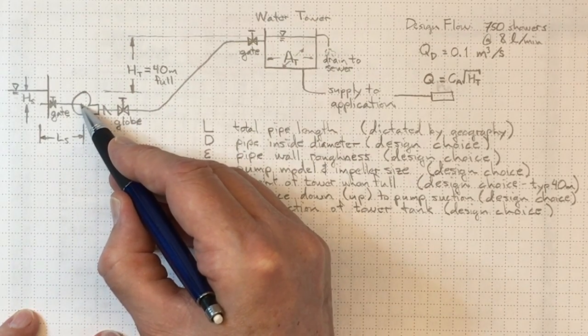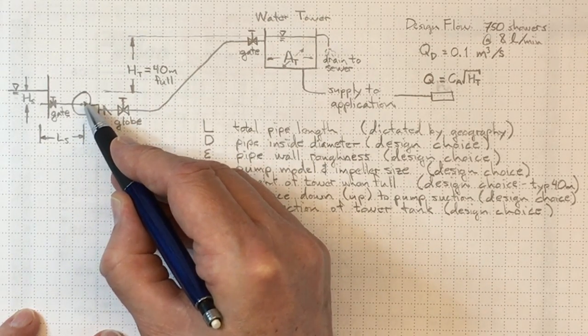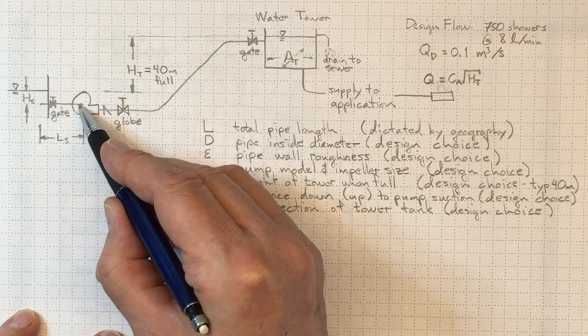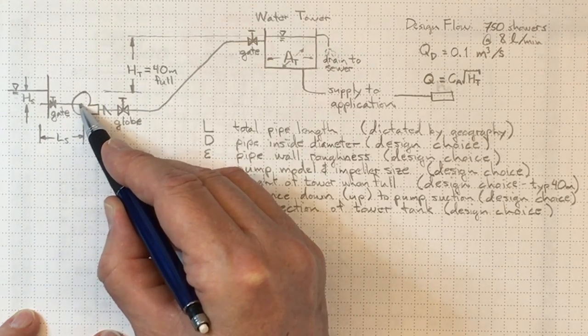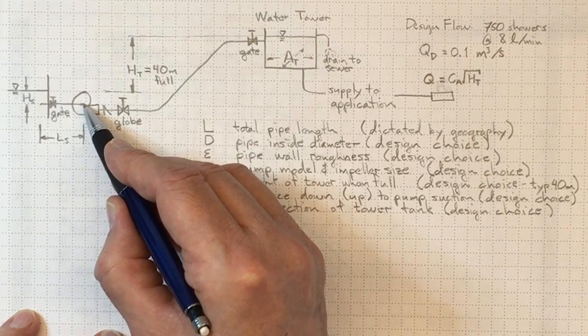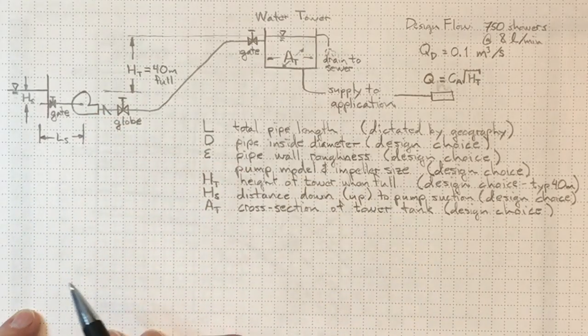So if we want to figure out the NPSH here and make sure we're not going to have a cavitation problem, then we're going to have to look at the difference between the NPSH that we have available, that is what the pressure actually is here, and the NPSH that the pump requires here, what the pressure must be in order to avoid cavitation.